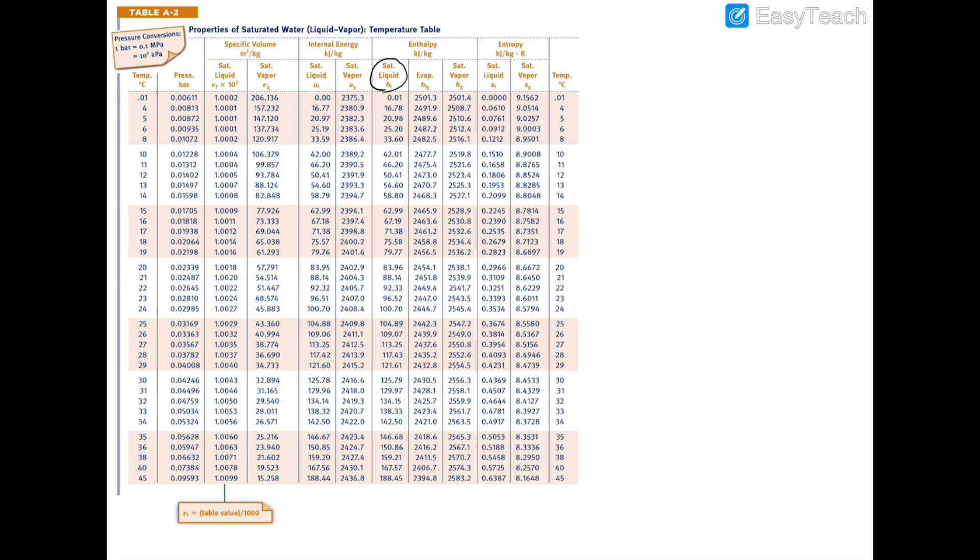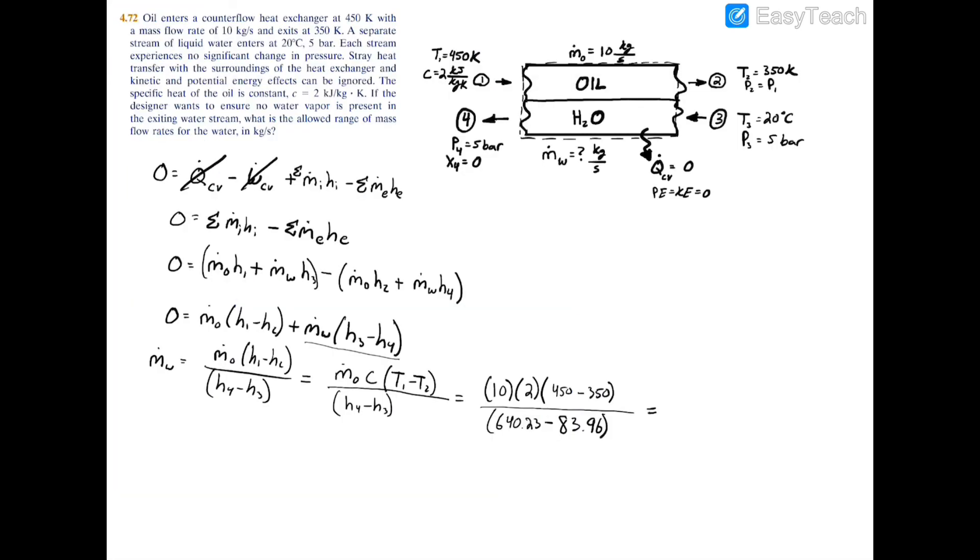So we can approximate using the saturated liquid specific enthalpy of 20 degrees Celsius for water, and we'll have 83.96 kilojoules per kilogram. If you plug this into your calculator you'll find that your mass flow rate of your water is equal to 3.595 kilograms per second.